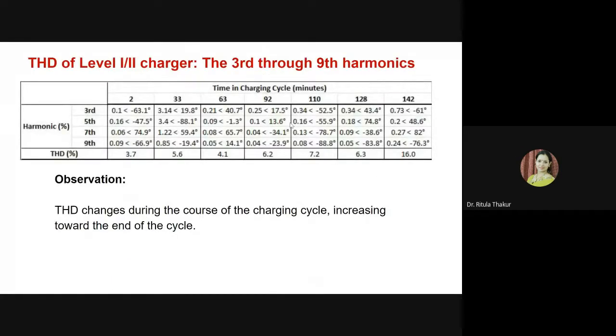And these are some of the tables that they had given, the THD of level 1 and 2, that is, single phase charger. So for the third through ninth harmonics, these are some of the readings, as well as the THD percentage they have given. This is the total time of the charging cycle, starting from 2 minutes to 142 minutes. We can see that initially it was very well within the range at 3.7%. We know that according to IEEE, it should be within 5%. But as the charging cycle came to an end, this had increased to 16%. So we can say that THD changes during the course of the charging cycle, increasing towards the end of the cycle.